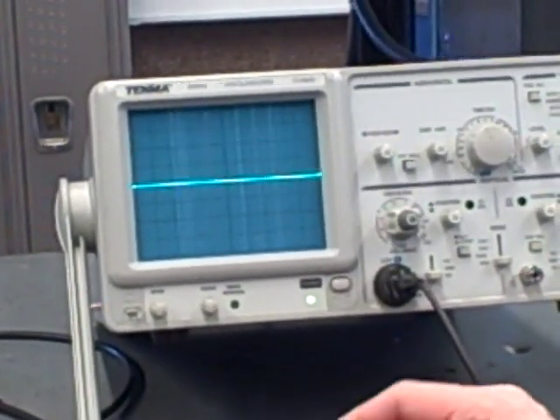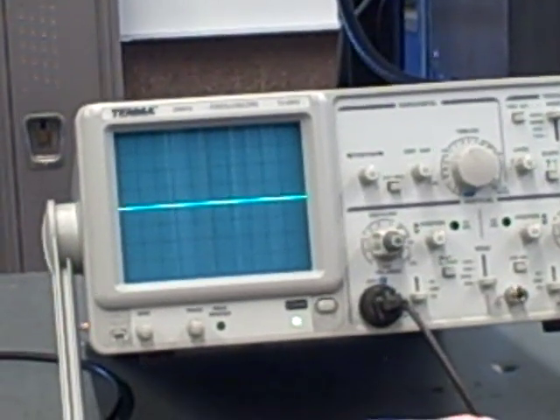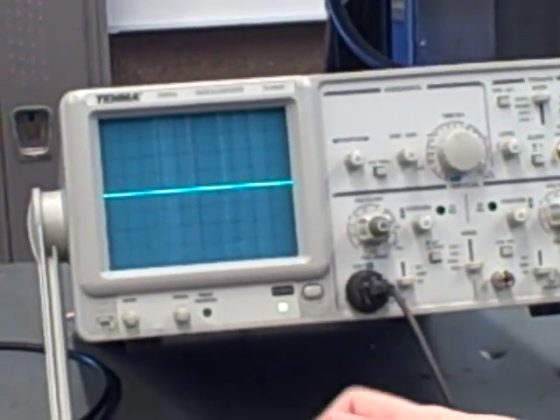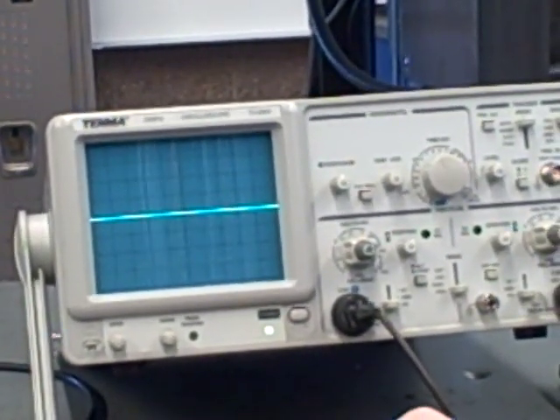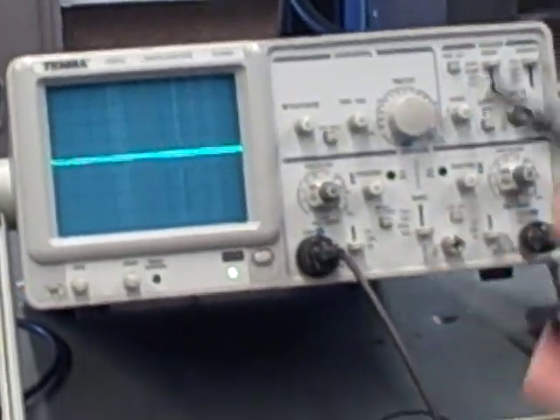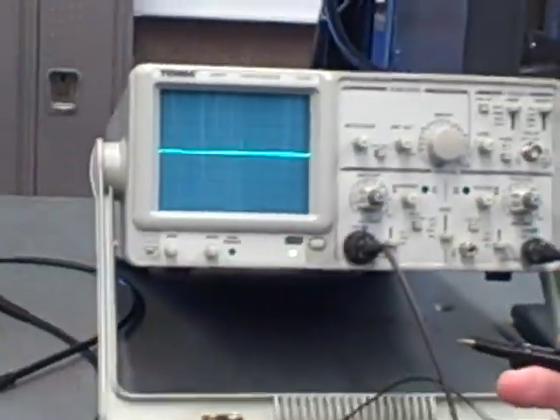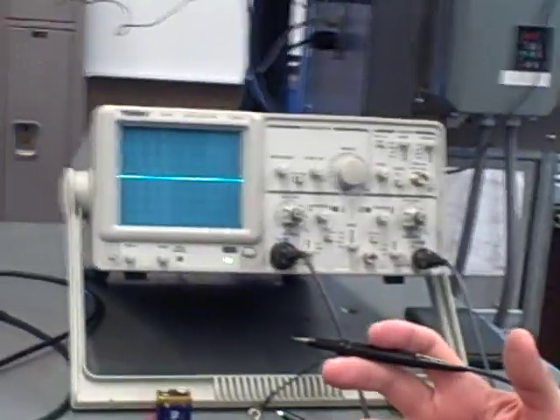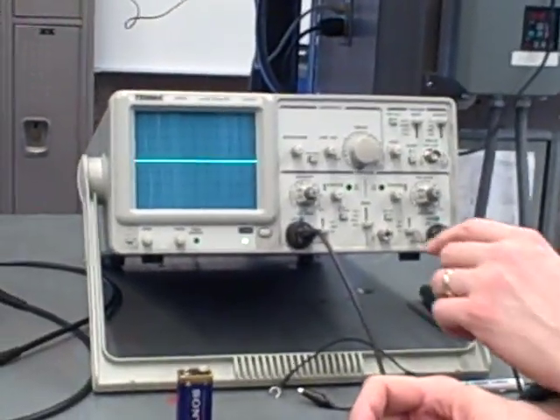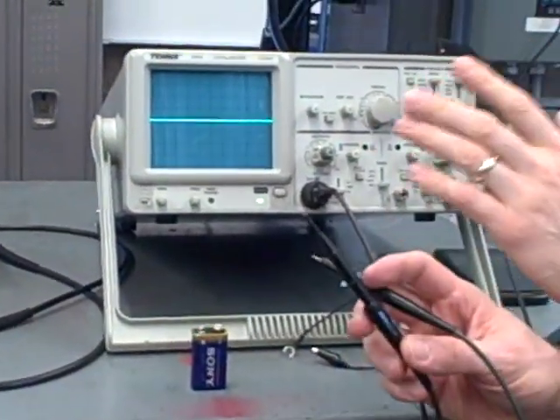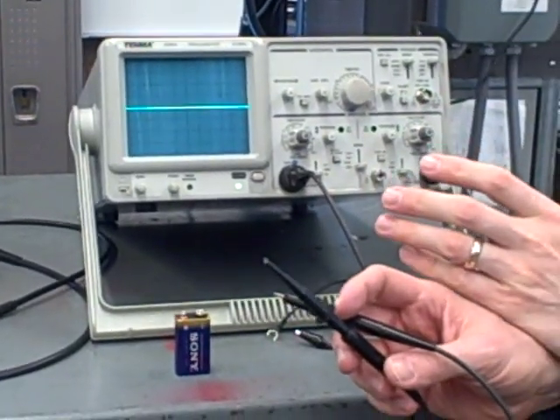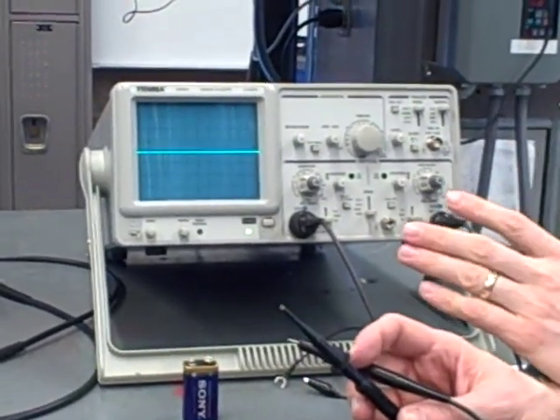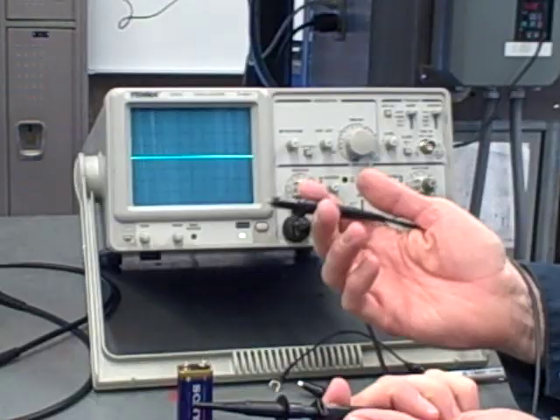So what I have is the ability now to measure 9 volts DC without forcing either terminal of the battery to go to ground potential. This is something usable in a live AC circuit. Now the only question we have, and the only problem we potentially have, is making sure we have enough range on our inputs with the 10 to 1 probes to measure the magnitude of voltage we're looking for. Once we've got that covered, we've already eliminated the grounding problem.